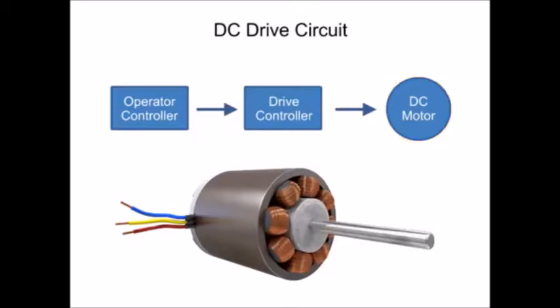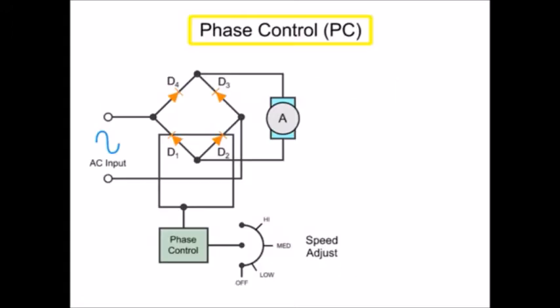Let's look at the phase control method in a bit more detail. Phase control works by modulating a gated diode-like device, such as a silicon-controlled rectifier or SCR, into and out of conduction at a predetermined phase of a rectified AC half-wave.